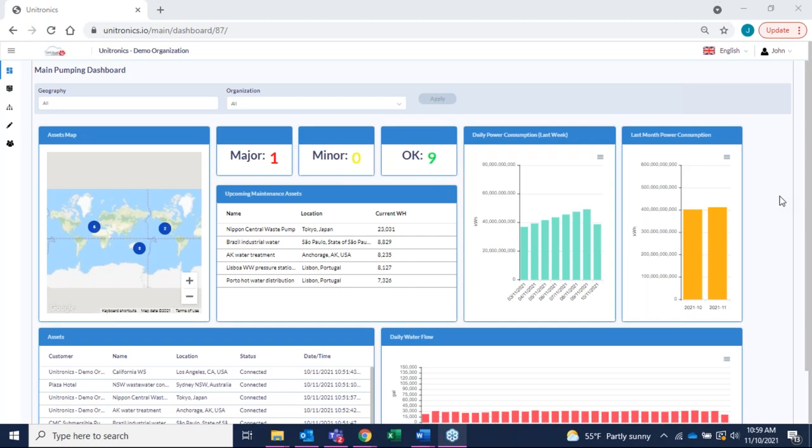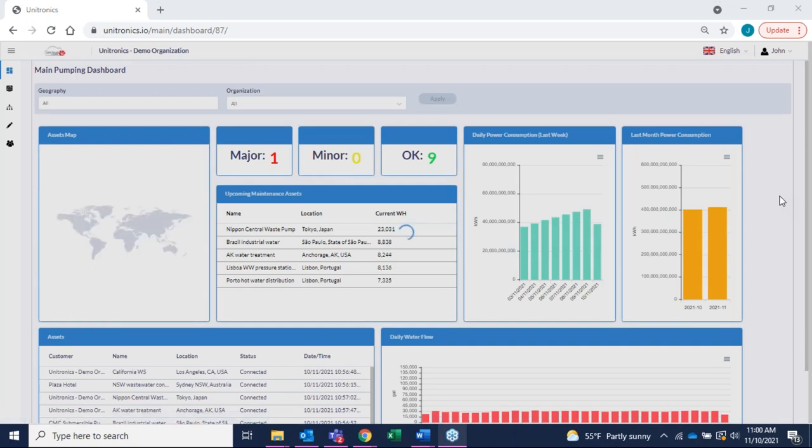To take this one step further, we now do support third-party PLC communication through our router, or any Modbus capable device really, through our router up to our cloud. So that is what gives you the ability to add a Jazz or a standard Vision Series controller, or any third party like Panasonic, Siemens, anything that supports Modbus as a slave configuration. The router is going to communicate Modbus master to that device, pull its tag values, and send it via MQTT up to the cloud.